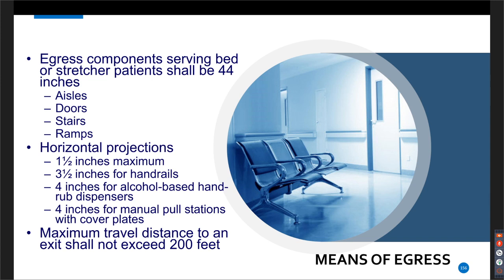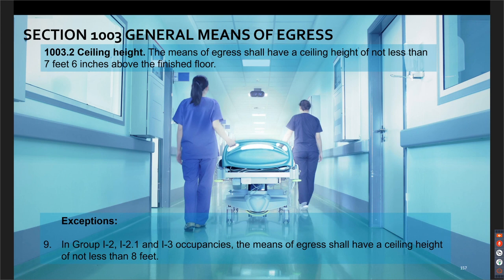And then maximum travel distance to an exit shall not exceed 200 feet. So yes, you heard us talk about 200 feet before to a smoke barrier. They have to be able to reach a smoke barrier in 200 feet and an exit in 200 feet. They're not always the same, though they often are. So please make sure you're looking at those individually.